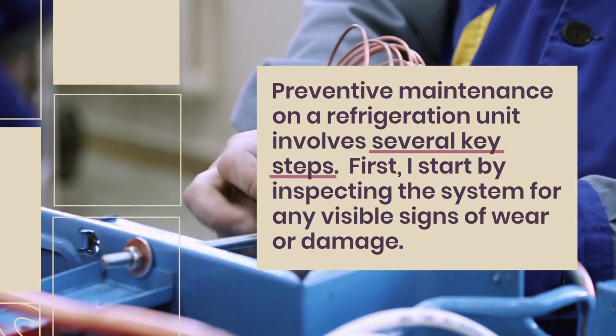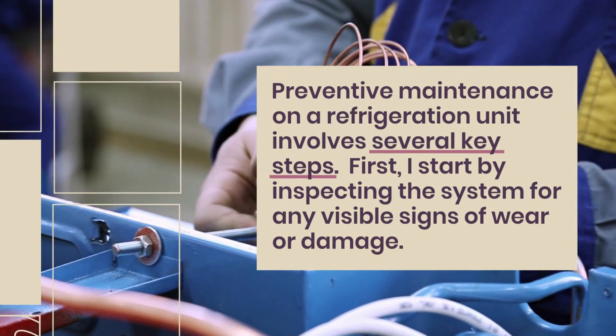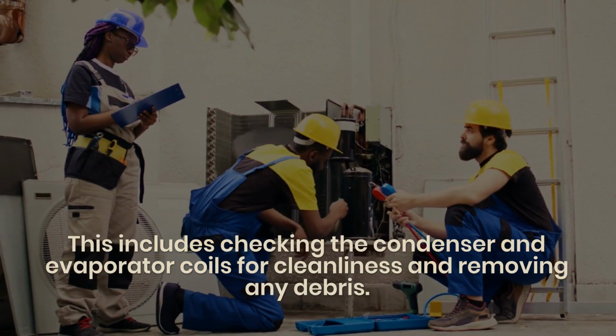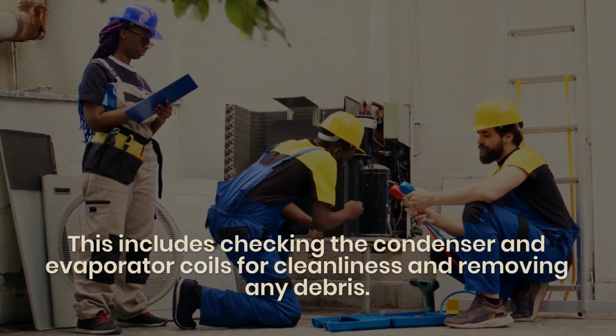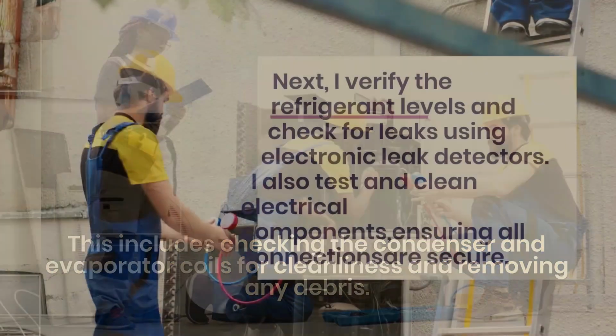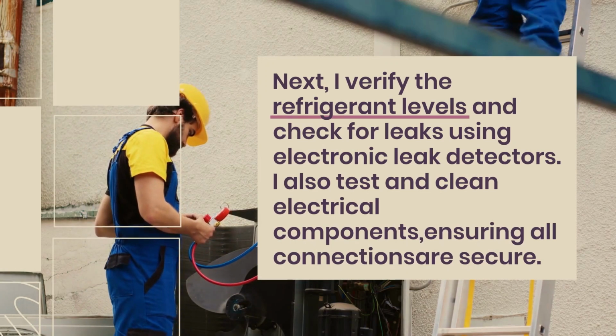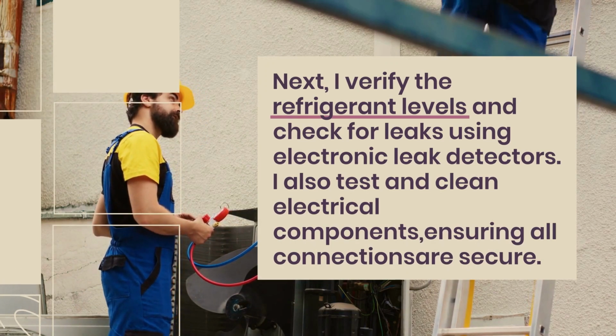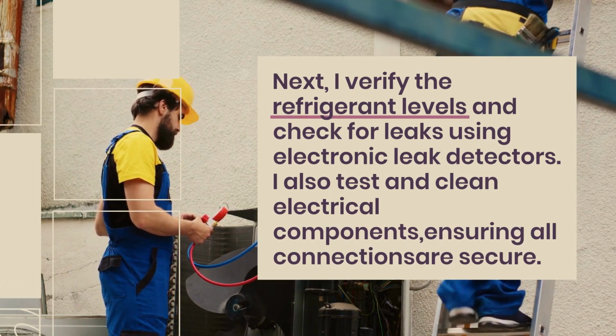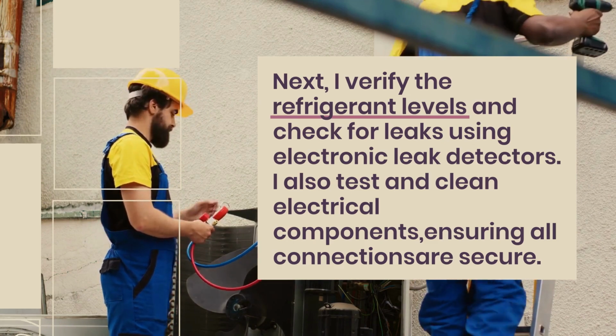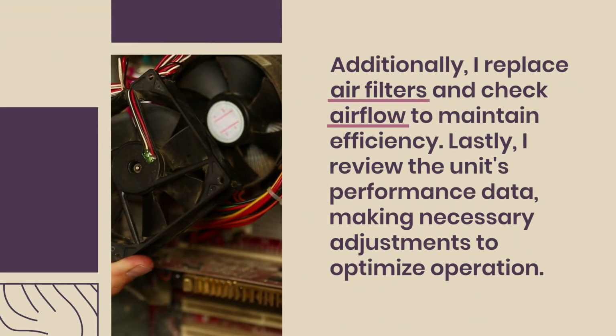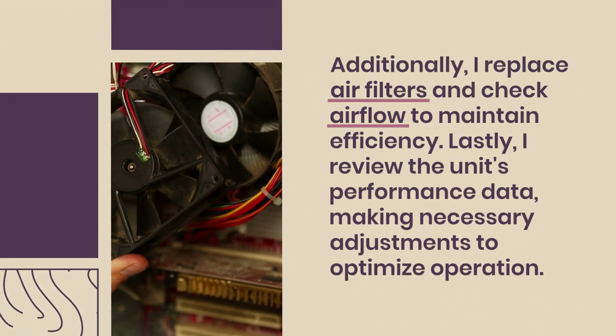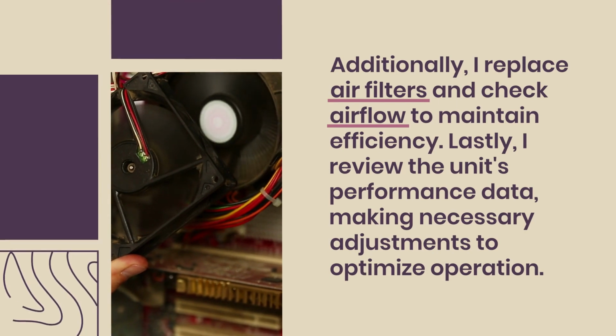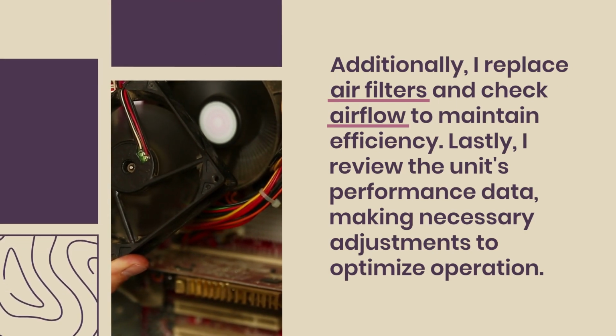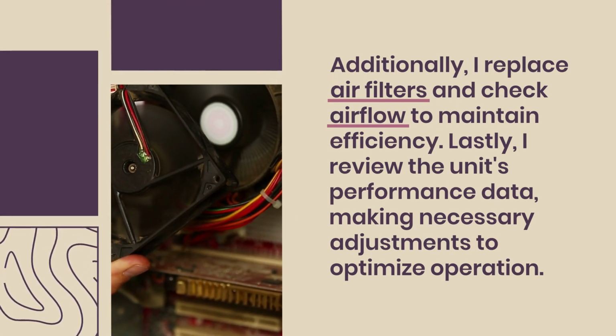First, I start by inspecting the system for any visible signs of wear or damage. This includes checking the condenser and evaporator coils for cleanliness and removing any debris. Next, I verify the refrigerant levels and check for leaks using electronic leak detectors. I also test and clean electrical components, ensuring all connections are secure. Additionally, I replace air filters and check airflow to maintain efficiency. Lastly, I review the unit's performance data, making necessary adjustments to optimize operation.